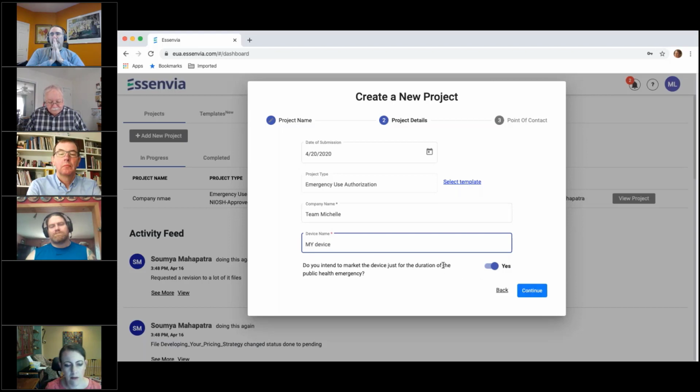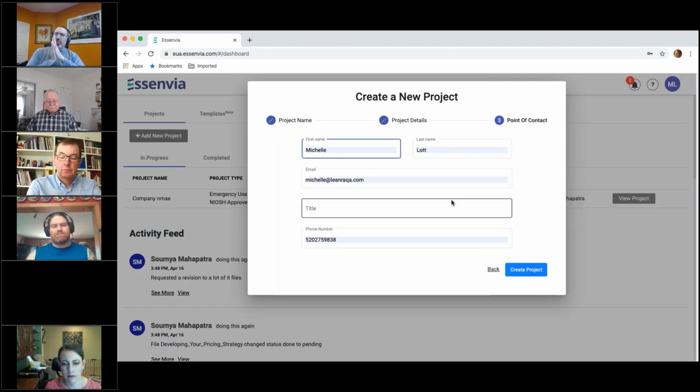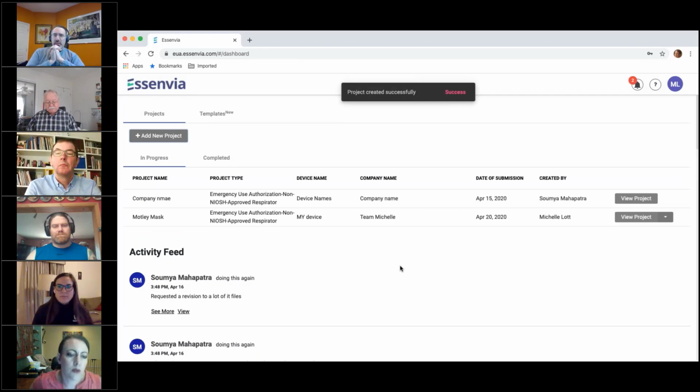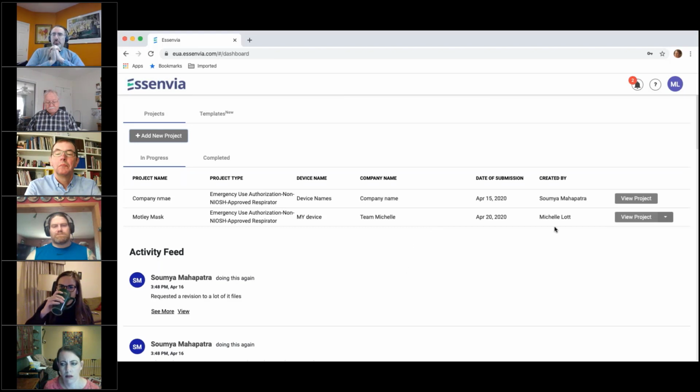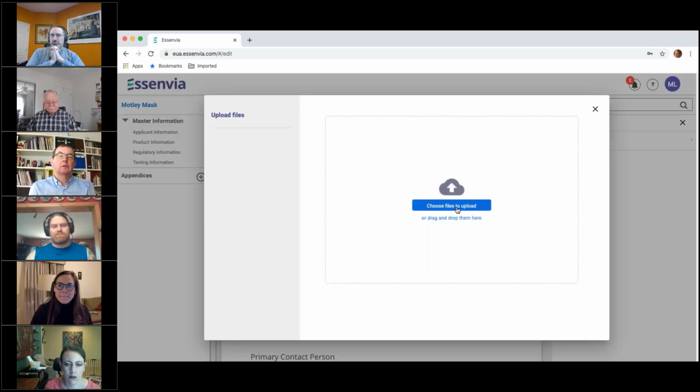I have to indicate, am I marketing this just for the duration of the public health emergency, or do I plan on submitting a 510K? Didn't you teach me that the whole premise of EUA is that you mean to stay in market afterward? You're supposed to at least fake it? No, you just can't stay in market afterwards unless you also bring it to market legally. So you upload your logo.